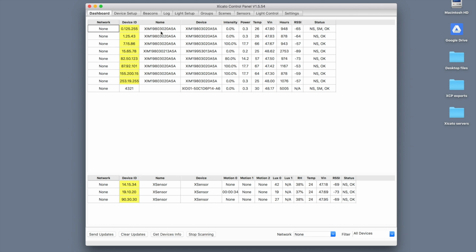A device ID is a unique number between 1 and 32,767 that is the unique logical address of a node in a Xicato Bluetooth network. Since the ID will be encrypted, the device ID has to be unique only within a particular secure network. But it is good practice for a device ID to be globally unique at a particular site in case you decide to move it to a different network sometime in the future. Obviously, this is not possible if you have more than 32,000 nodes at a site.